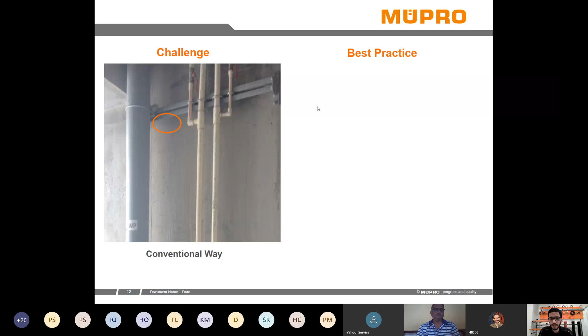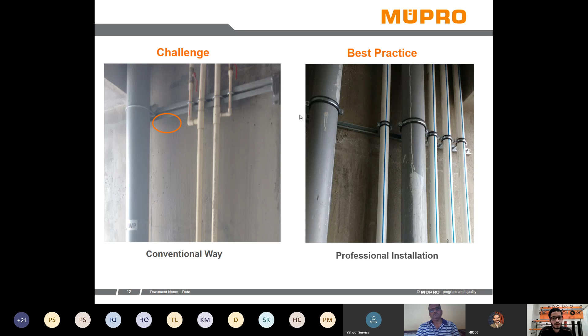So now let's see how this same support can be installed in a modular way with the help of MUPRO supports. Now this same kind of service is supported with the help of a MUPRO support. You can see how heavy the bracket is at the back end. Here it is a sleek, single channel placed on the wall, and a proper firm grip clamp is used for all the pipes, and there is flexibility of changing the position of the pipe as per the requirement just by loosening the nuts. You can slide the pipe along the length of the channel.